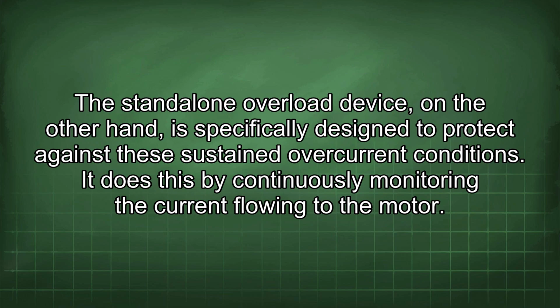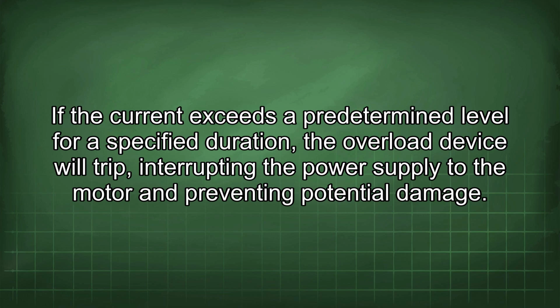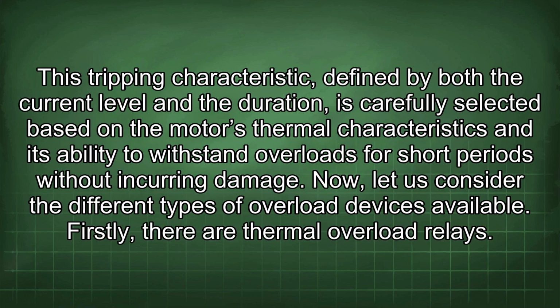The standalone overload device, on the other hand, is specifically designed to protect against these sustained overcurrent conditions. It does this by continuously monitoring the current flowing to the motor. If the current exceeds a predetermined level for a specified duration, the overload device will trip, interrupting the power supply to the motor and preventing potential damage. This tripping characteristic, defined by both the current level and the duration, is carefully selected based on the motor's thermal characteristics and its ability to withstand overloads for short periods without incurring damage.